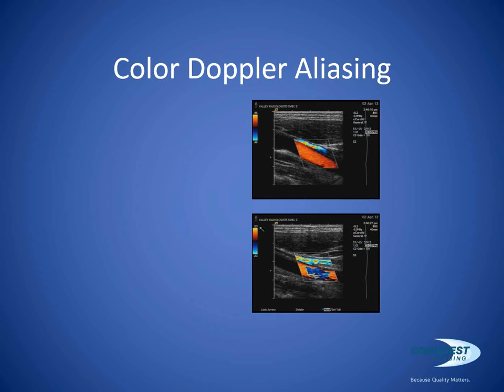I didn't automatically induce plaque into my artery. All I did was take my Doppler scale and adjust it too low. By adjusting it too low, I was able to make the system look like it's malfunctioning. It's a little challenging to determine this, but I just wanted all of you to be aware of the term and to be able to recognize it when you're looking at a machine, if somebody complains about ultrasound color Doppler inaccuracy. So in the top image, I set the scale properly. The bottom image, I intentionally adjusted it improperly.